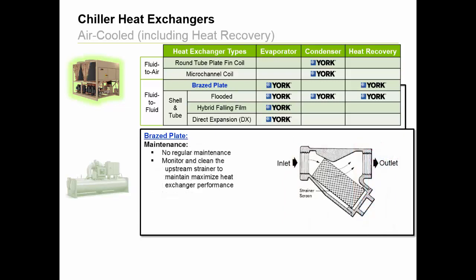Regarding maintenance, there are no regular requirements, as these heat exchangers are used in a closed loop. However, since brazed plate heat exchangers are inherently not accessible for cleaning due to their design, it's important that a strainer be installed upstream to protect against the potential for heat exchanger clogging or freezing. Meaning, in new facilities, there could be dirt or debris in the chilled water loop from building construction, or in older buildings, pipes could be eroding, causing material buildup.